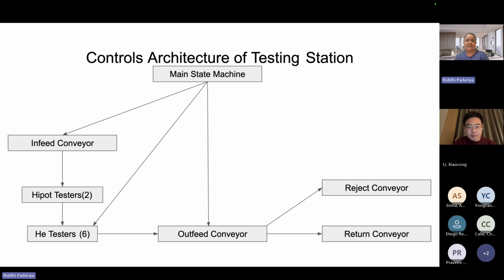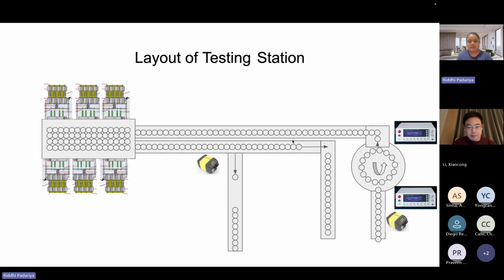Briefly, the way we laid out the controls architecture of the testing station looked something like this. We had a main station that turned all the conveyors on and off by clicking the start button on the human machine interface (HMI). The only thing that wouldn't turn on automatically was the helium check modules coming down on the cell. They would only come down if there were cells that hadn't been tested yet, and we stored that information in the PLC as testing was happening.